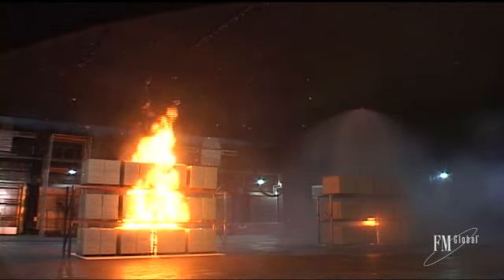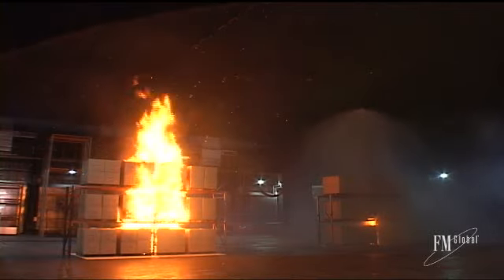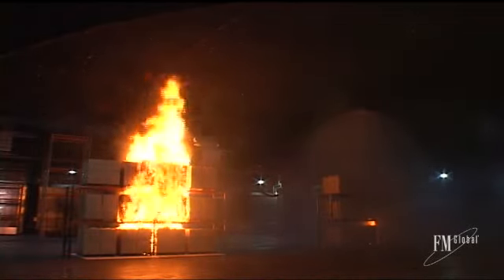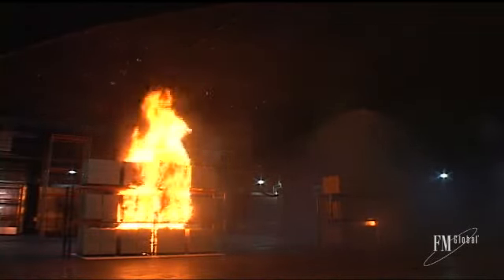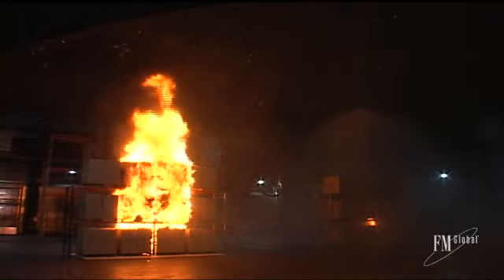At the other property, a disaster is unfolding. Ceiling temperatures are now exceeding 540 degrees Celsius and the overhead steel begins to lose its strength. Steel can withstand these temperatures for no more than 10 minutes, and the higher the temperature gets, the shorter that window becomes.